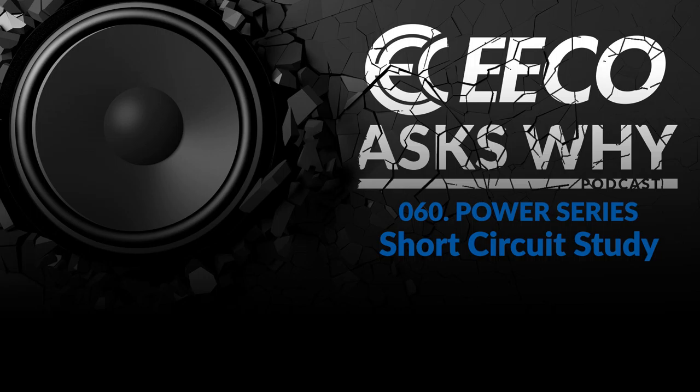So in order to perform a short circuit study, you need protective device manufacturer's data and also the available maximum current that protective device will experience during that fault. Today we use electrical transient analysis software such as ETAP, Easy Power, SKM to help automate the process and cut down on time. However, in my opinion, it's still very important that the engineer performing the study know what the program is doing to help spot any potential errors or unreasonable values when they're performing this study.